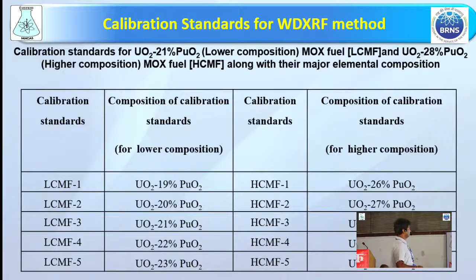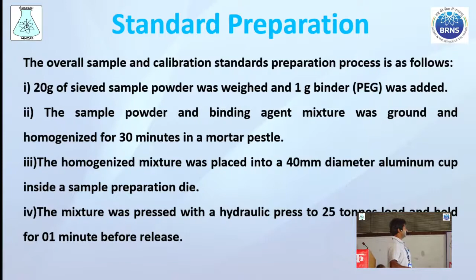For the standard preparation, first of all we have prepared master standards. We have 20 grams of one sample mixed with the UO2 as per the standard I have already shown in the slide, mixed with polyethylene glycol, put in the aluminum cup, and pressed with the hydraulic press having 25 ton capacity for 1 minute. These are the main parameters for the hydraulic press.